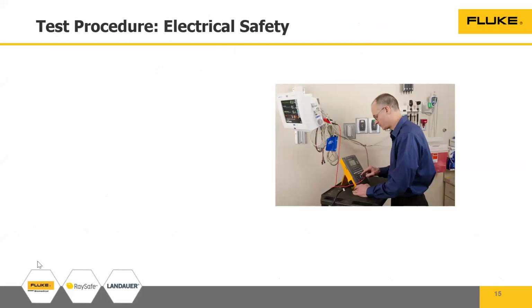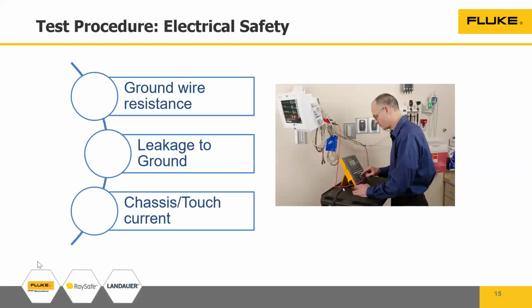So basically, what is the bare minimum you need to do, and what tests do you need to do? Ground wire resistance, leakage to ground, chassis or touch current. There might be a query: why chassis or touch current, how can there be a touch current? Suppose you have a patient monitor or a ventilator, which mostly has a plastic, non-conductive body, so why would there be current in that?